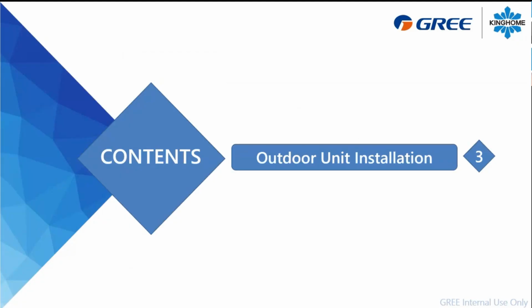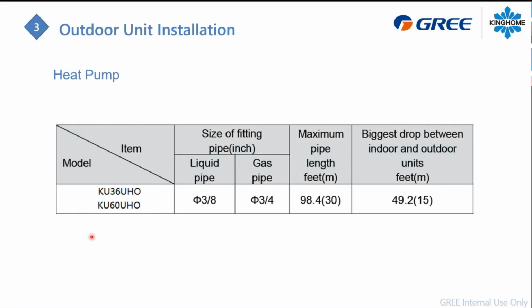We're going to move forward with the outdoor installation. As I said earlier, we have two types of outdoor unit. It's called a 3-ton and a 5-ton, but it's configurable as a 2-ton or a 4-ton unit. Either way, the piping sizes will be 3/8 and 3/4 for any kind of installation. The maximum pipe length is 98 feet, and the biggest drop you can have between the indoor and the outdoor unit is 49 feet.